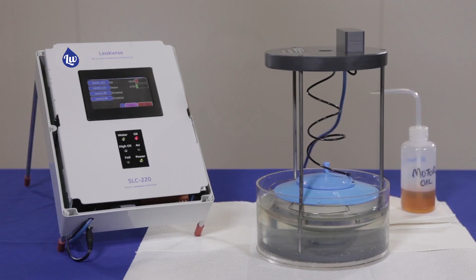Now, how do we communicate that to the outside world? We've got a number of ways of doing that: RS-232, RS-485 Modbus, alarm contact closures, 4-20 milliamp outputs that follow the thickness change, GSM text messaging which we can send to multiple human users with different phone numbers and different messages, and the ability to send GSM text messaging to computers. So a very, very flexible way of getting the communication out to the end user when he needs it.